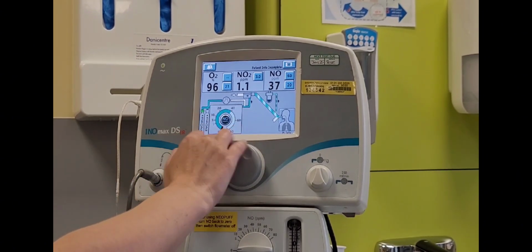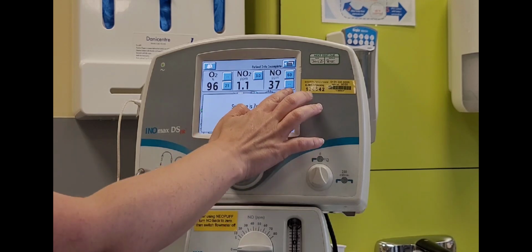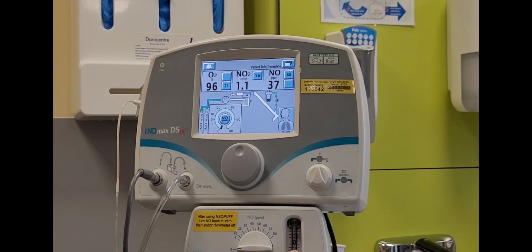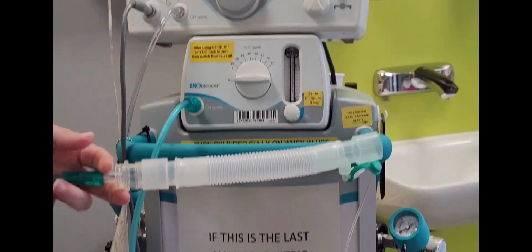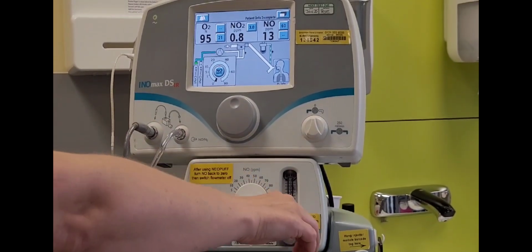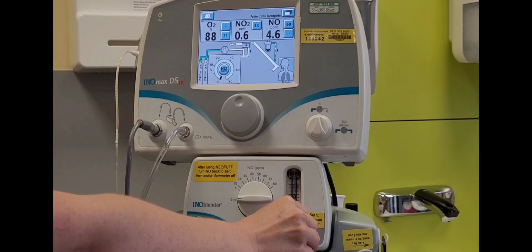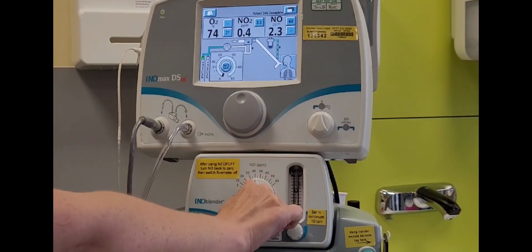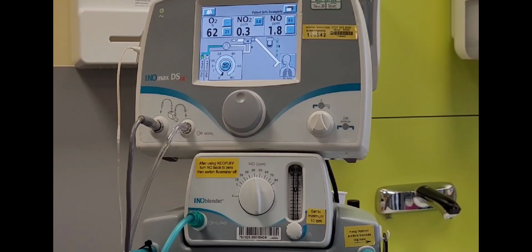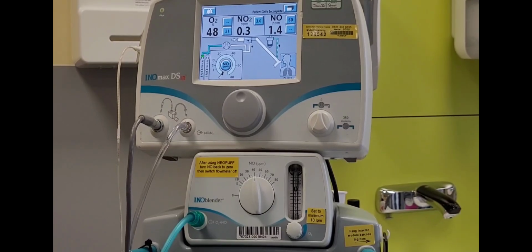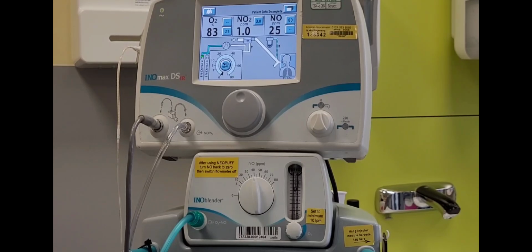To test the INO blender, remove the oxygen from the wall and attach it to the front of the machine. Remove the injector module from the pre-use setup. Set the dose on the blender to 40 and the flow to 10 litres. Check that the NO values are between 32 and 48. This can take a few minutes. Once achieved, turn the dose back to 0 and remove the oxygen from the front of the machine. Place the injector module back into the pre-use setup.